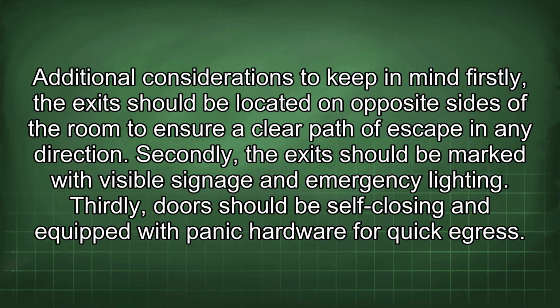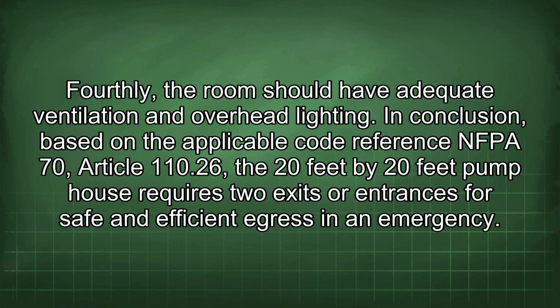Secondly, the exit should be marked with visible signage and emergency lighting. Thirdly, doors should be self-closing and equipped with panic hardware for quick egress. Fourthly, the room should have adequate ventilation and overhead lighting. In conclusion, based on the applicable code reference NFPA 70 Article 110.26, the 20 feet by 20 feet pump house requires 2 exits or entrances for safe and efficient egress in an emergency.